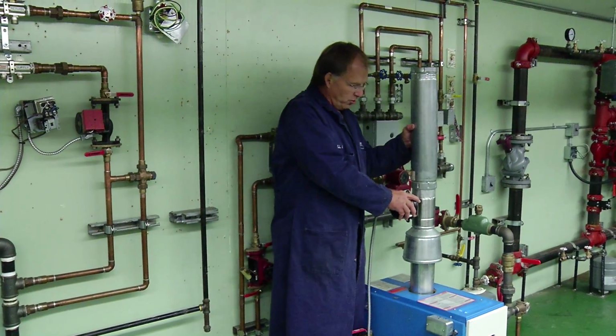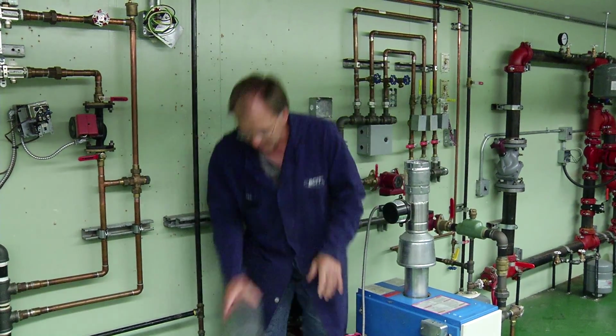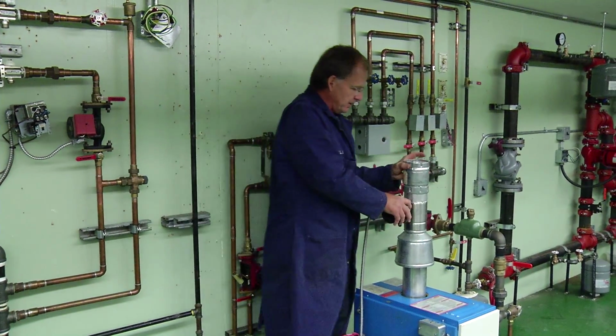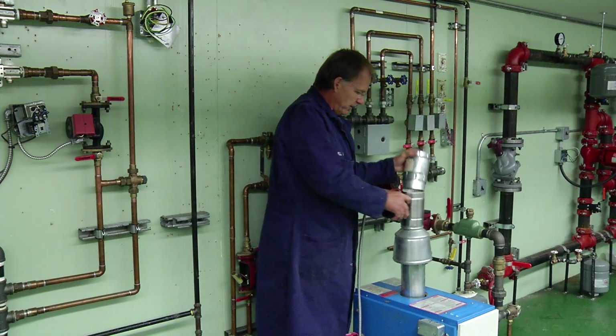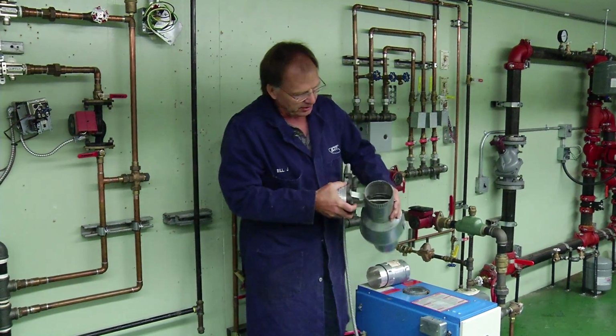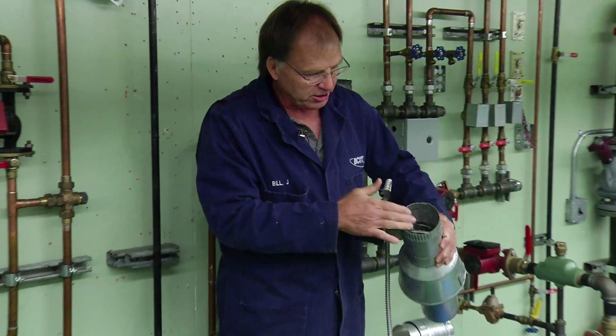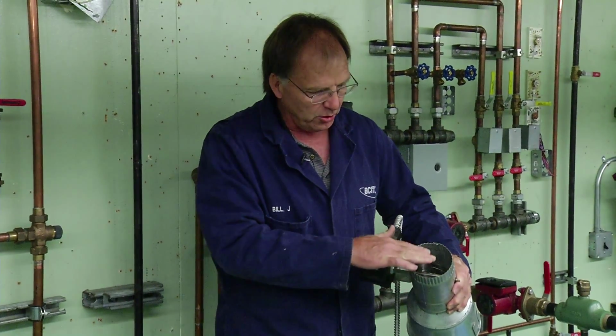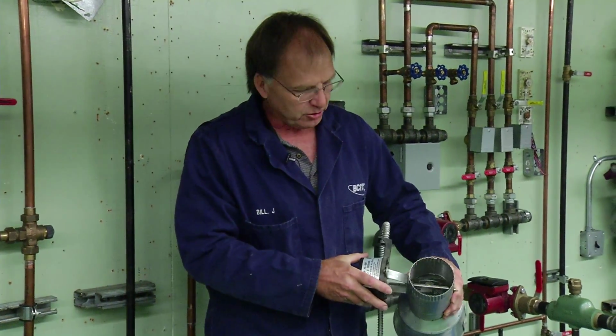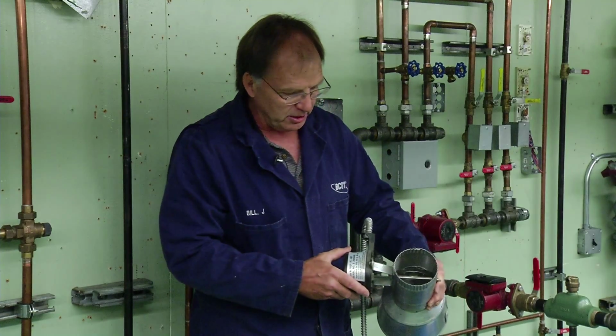I just wanted to show you the inside assembly. I'm just taking off the vent itself so that I can get at and show you the inside workings of these vent dampers. They're simply a plate or a valve that goes across the area of the pipe. It's driven by a motor. This motor is connected to the actual control system in the boiler. Right now, this valve, or this butterfly valve damper, is open.